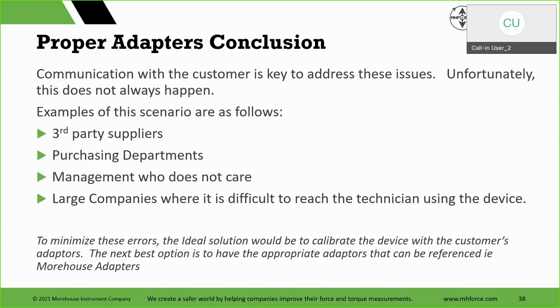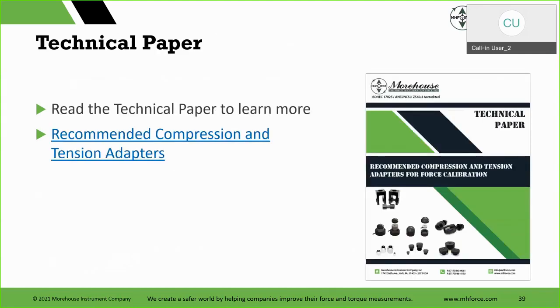The ideal solution is always going to be to calibrate the device with the customer's adapters, or have the customer send the appropriate adapters to the reference lab for cal. Secondary is to document what you did, preferably use Morehouse adapters, get the okay by the customer, and then go. We have more that can be said about this. We have technical papers on adapters. This one was one of the best papers at NCSLI. Very, very proud of it. It's in the PDF link if people want to read it.